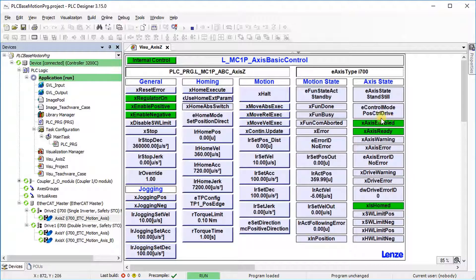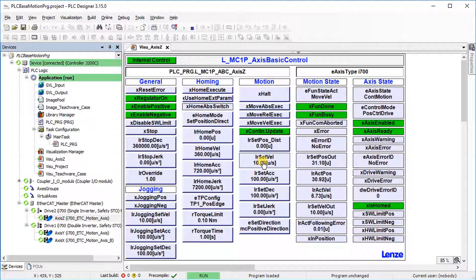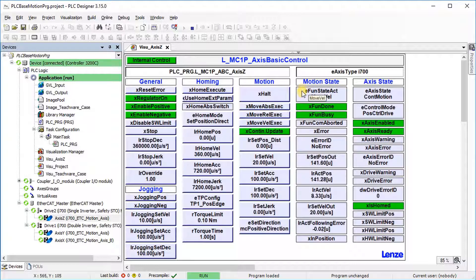The axis should be enabled. Continuous update accepts changes cyclically; the profile parameters are accepted continuously during execution. Assign a rising edge to the move velocity execute input. The continuous travel starts on the basis of the parameters for the motion profile. The technology module changes to move velocity state. This function can be aborted via the stop input.